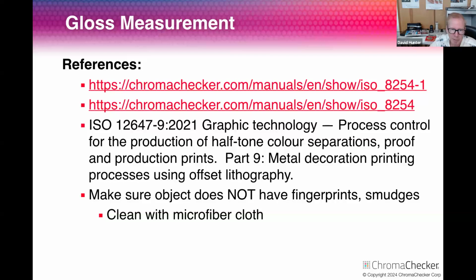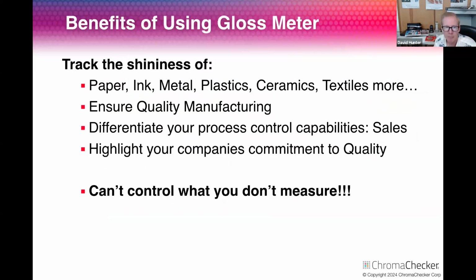Another thing you want to be clear of is, in the gloss meter calibration, there's a black shiny tile, almost like an iPhone screen when it's turned off. You want to make sure you use a microfiber cloth to clean it. Just earlier today, I looked at it and there's a big old thumbprint on there, and it had to have been mine. I'm very cautious not to touch it, and yet somehow I touched it along the way. So you want to make sure it's nice and clean, and then you store the instrument in that holder.